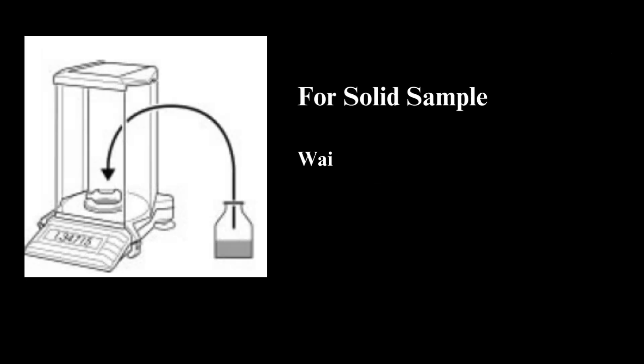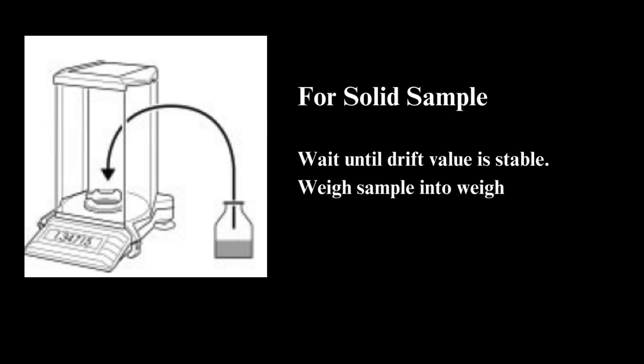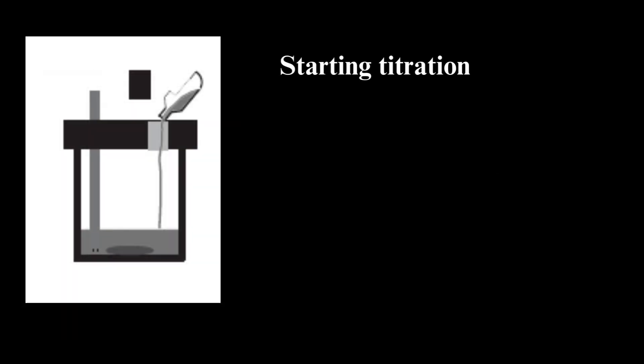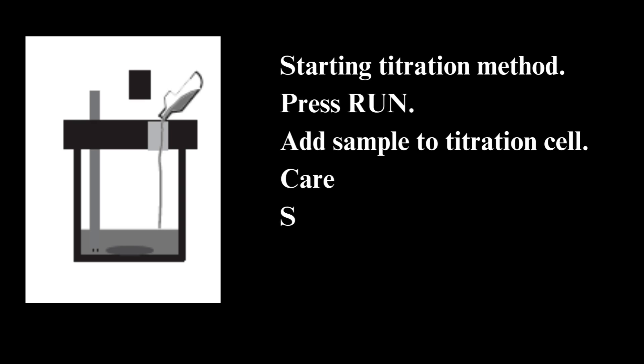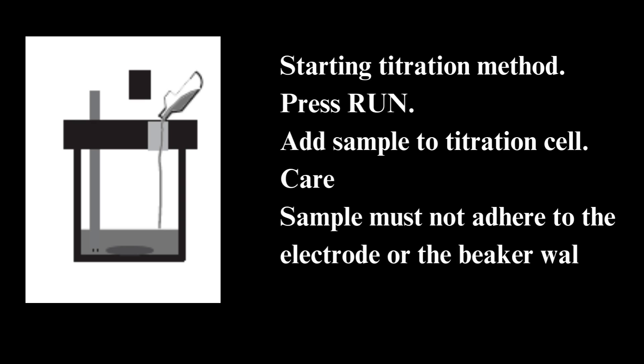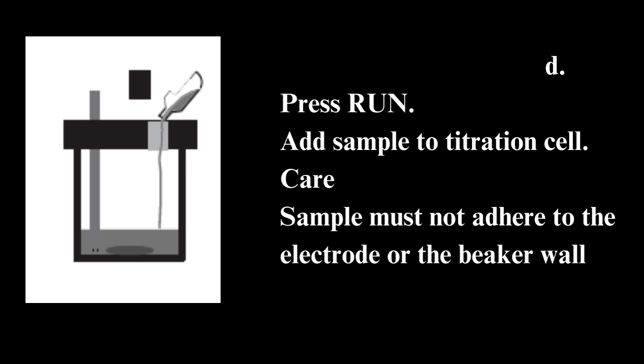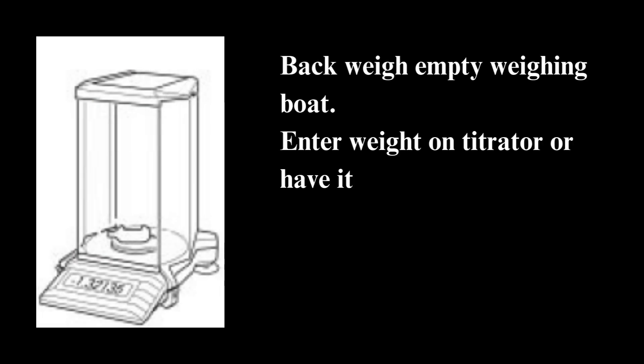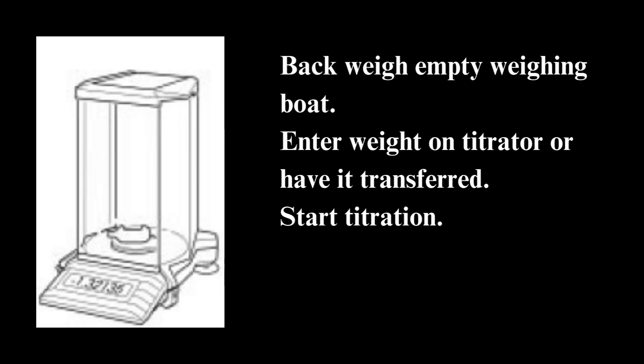For a solid sample: wait until the drift value is stable. Weigh the sample into a weighing boat and tare the balance to zero. Start the titration method and press run. Add the sample to the titration cell — the sample must not adhere to the electrode or the beaker wall. Back-weigh the empty weighing boat, enter the weight on the titrator or have it transferred, then start the titration.